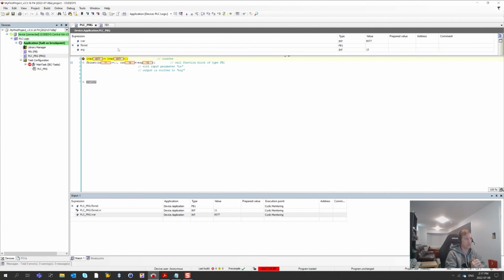What you're looking at here is the sequence of operation of the PLC, on how it's executing each line of code. That's why it's really important not to repeat outputs and have them in different lines of code, because you get all kinds of weird stuff happening from this sequencing.